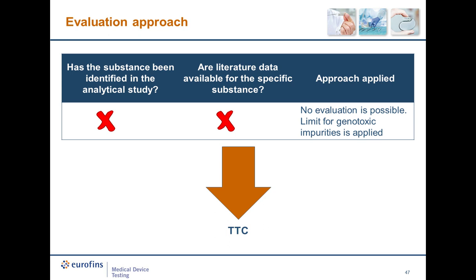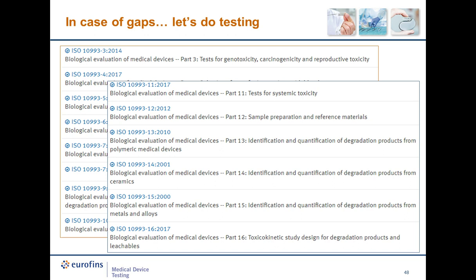At the end of the toxicological evaluation, as mentioned before, we should be able to evaluate the actual likelihood for adverse systemic effects to occur during the clinical use of the device. In case we still have gaps in our knowledge of the biological risk, we are requested to perform some additional tests. We should refer to the several parts of the ISO 10993 series. You will find a relevant standard for each endpoint that needs to be addressed. For example, cytotoxicity is described in part 5, irritation in part 10, systemic toxicity in part 11, and so on. By the way, a lot of those standards are now under revision.